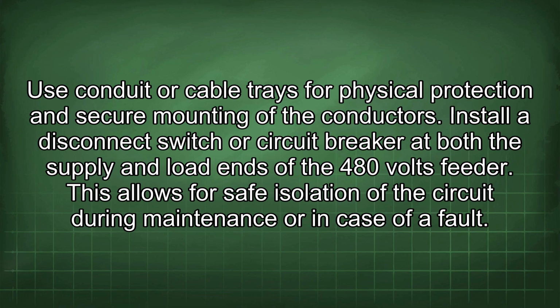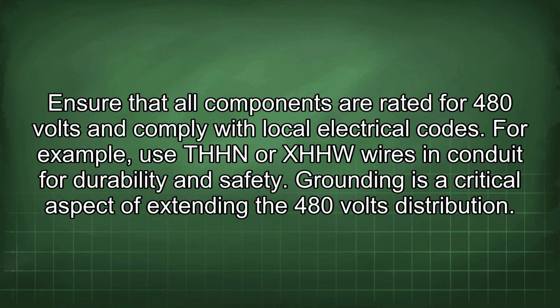Use conduit or cable trays for physical protection and secure mounting of the conductors. Install a disconnect switch or circuit breaker at both the supply and load ends of the 480 volts feeder. This allows for safe isolation of the circuit during maintenance or in case of a fault. Ensure that all components are rated for 480 volts and comply with local electrical codes. For example, use THHN or XHHW wires in conduit for durability and safety.